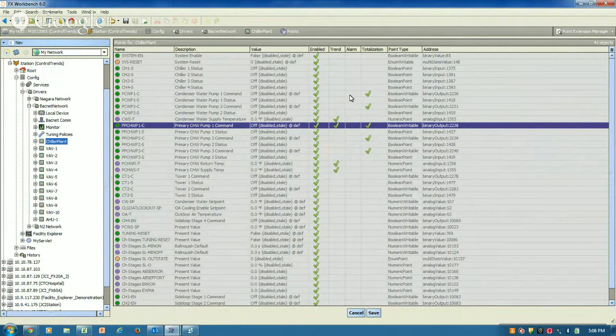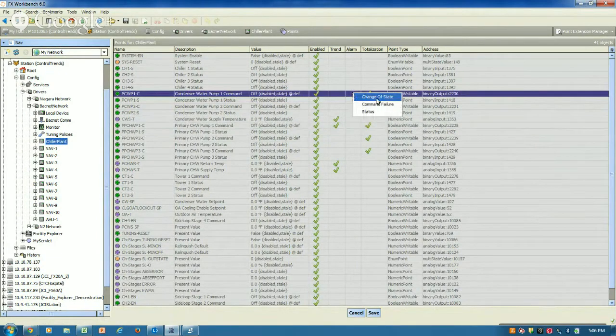If I wanted an alarm on something like condenser water pump 1 command, I click on that one and it'll alarm for a change of state, command failure, or status anytime I do that. So I've automatically added those trends onto there.